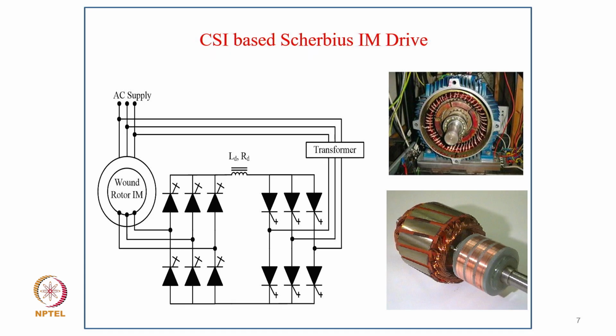It's also typically used in current source inverter based Scherbius type, where earlier we were using thyristors for this purpose. Now we use self-commutating devices like GTO or IGBT with a series diode. Because this is capable of operating in PWM mode, we are able to generate even leading reactive power, which is required for the machine in this wind application typically.